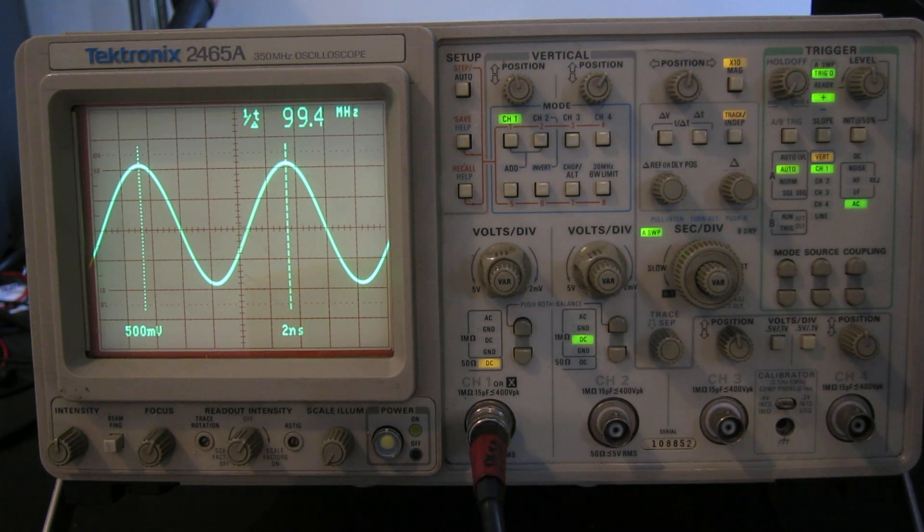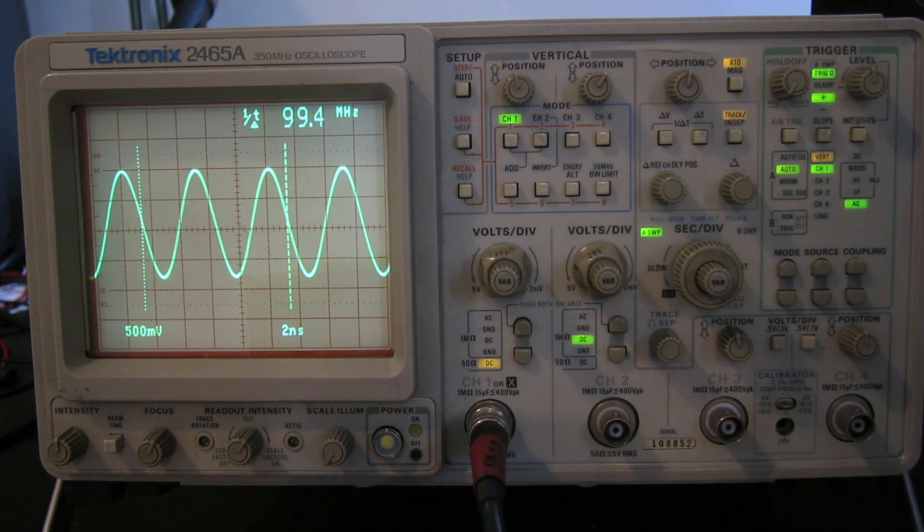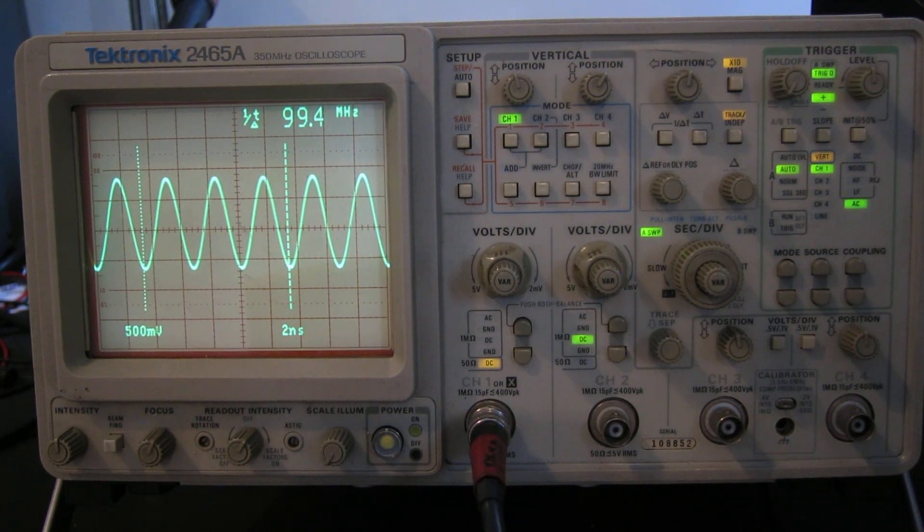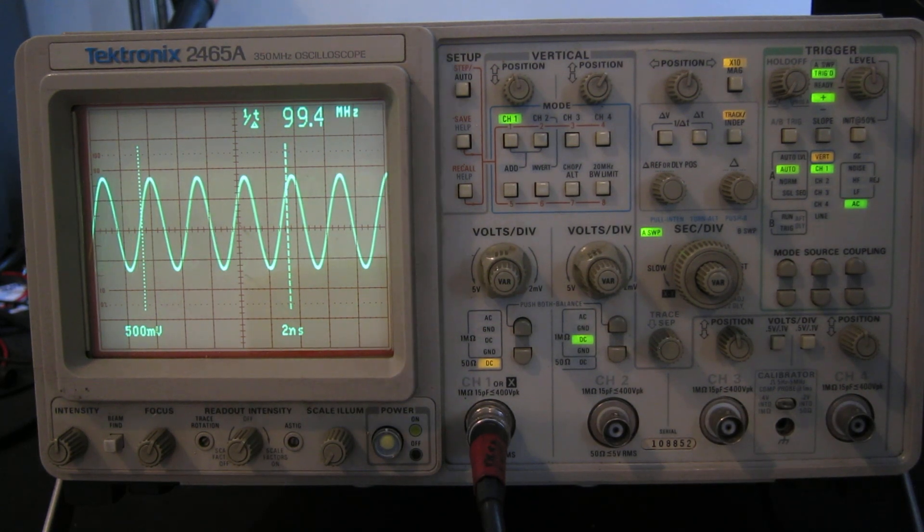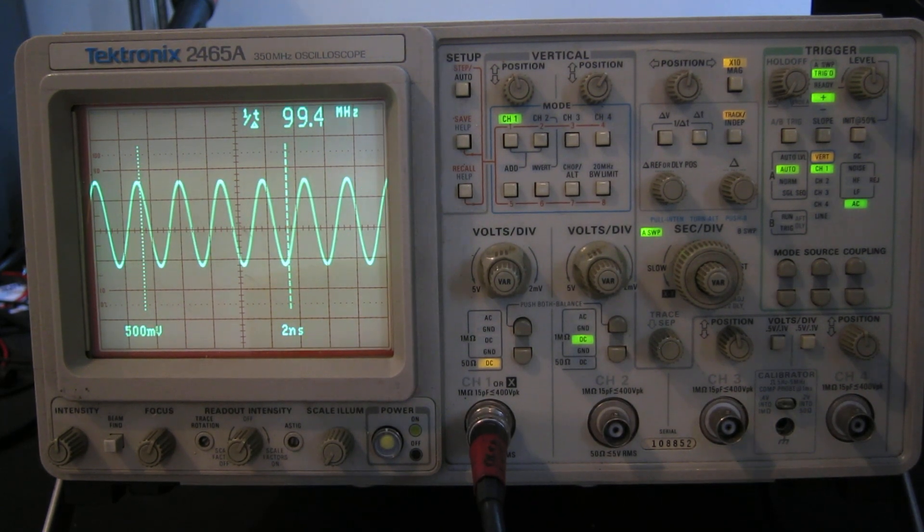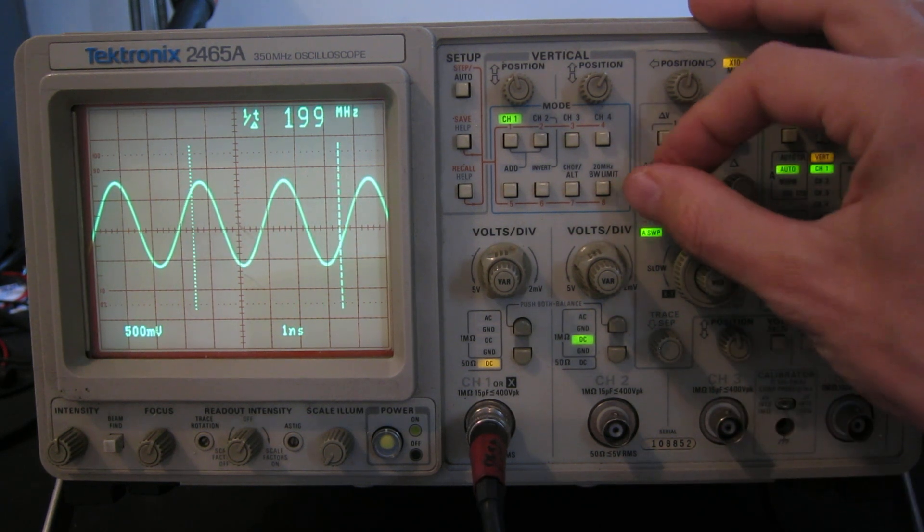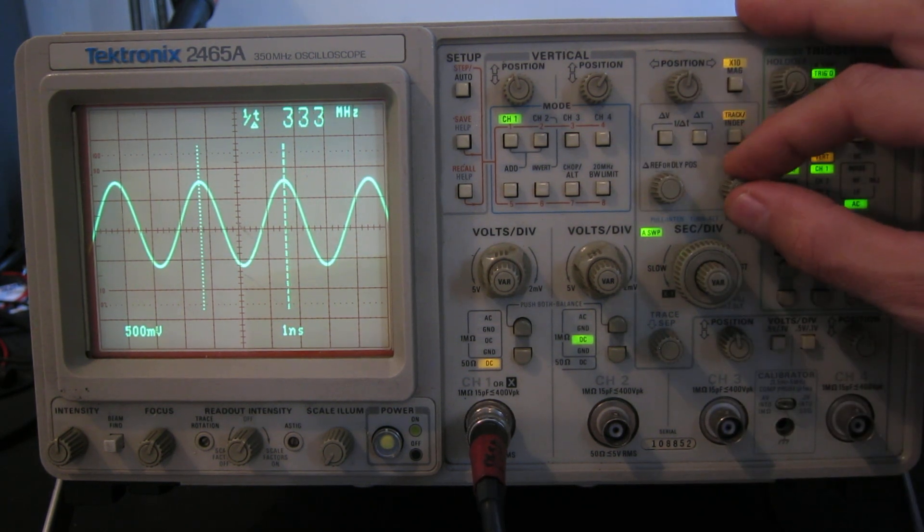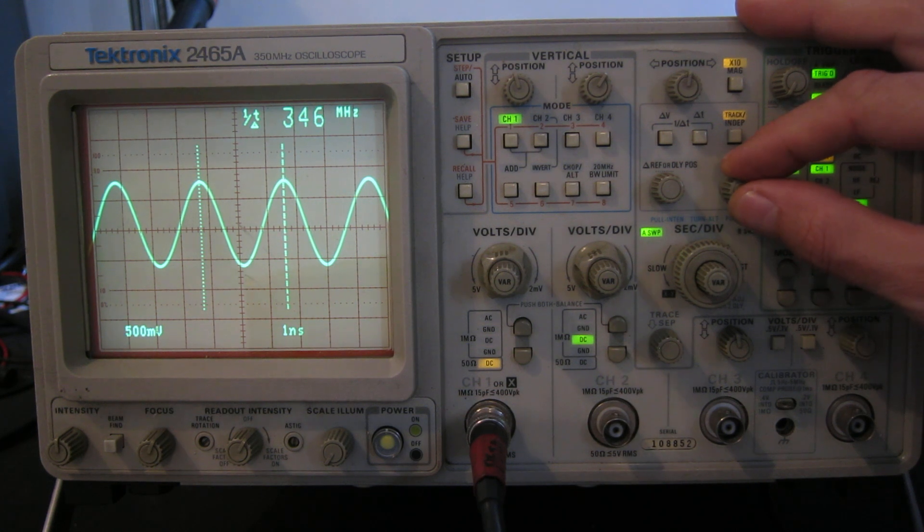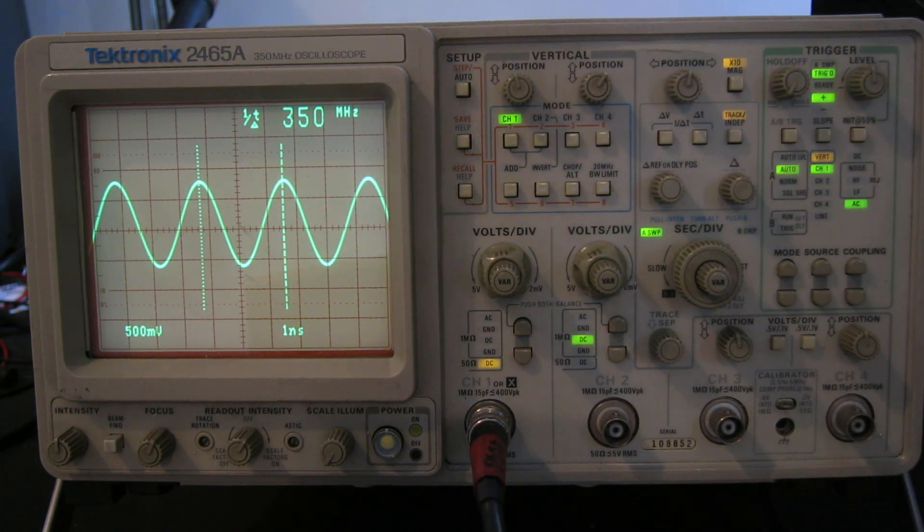That's a 100 megahertz signal, and I can increase the frequency of that. 200 megahertz, amplitude drops a little bit, as you'd expect. 300 megahertz, we will go 350 megahertz, which is the scope's minus 3 dB point. Just measure that between peak to peak. Here we go, 350 megahertz. But it carries on working well beyond that, actually. The amplitude drops off, obviously.